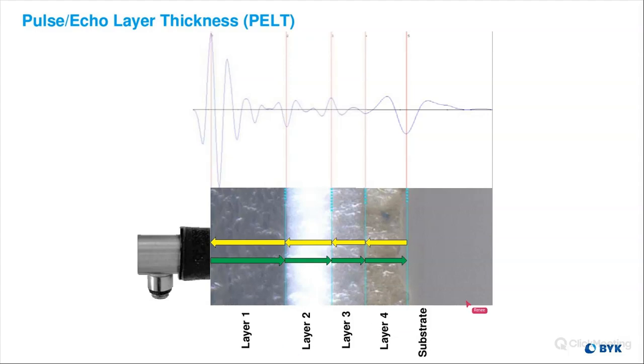So if I was to take this same microscope image that I showed you just a couple slides ago, you can see that this is the waveform output that you would see. This is like the display you would see on the PELT gauge. And as the sound goes through our coatings, this is our first big echo, and this is a little different than the M and W I just said. This is what we call our shim echo or our first echo. And the echo starts here right at the boundary between our cap and the top of our first layer. And then as we hit this layer boundary, we get an echo here. And then we hit our next layer boundary, get an echo, third layer boundary, an echo here, and our fourth and final layer here, our echo boundary before our substrate.